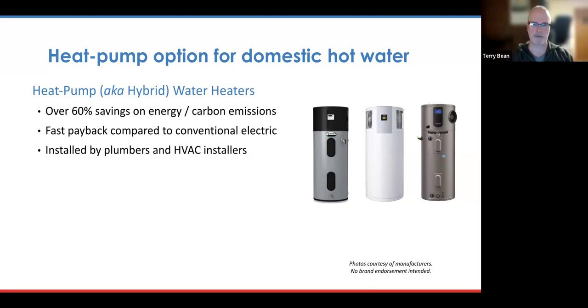Many of these systems, if not most of them these days, come as what they call hybrid systems, which means that they will revert to being a standard electric resistance hot water heater if there is a technical failure of that compressor on the top, which is nice. That means that if there's an issue, you'll still have hot water until you can get that compressor serviced. What's important to know is that this compressor that's on top of the unit would be drawing heat energy from a basement area. So they really aren't suited to being tucked into small, confined spaces like utility rooms. If you need to put them into an area like that, then you'd want to make sure that they have as much passive ventilation that affords them access to the larger volume of air in the basement as possible. That's really important.